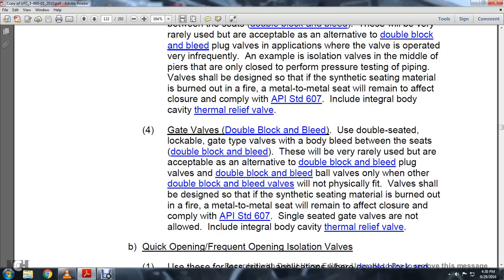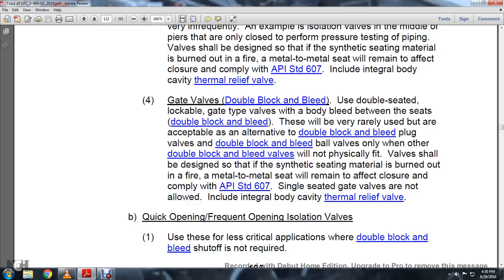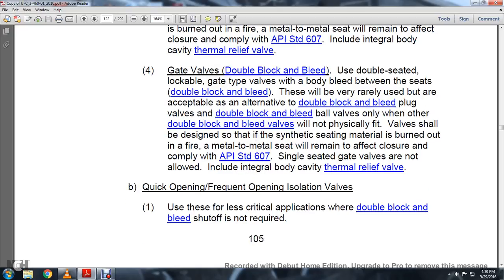Double block and bleed gate valves are used only when other double block and bleeds will not physically fit, and valves shall be designed so that the synthetic seating material is burned out in the fire and the metal to metal seat will remain to affect closure and comply with the API standard 607. Single seated gate valves are not allowed, including integral body cavity thermal relief valves.